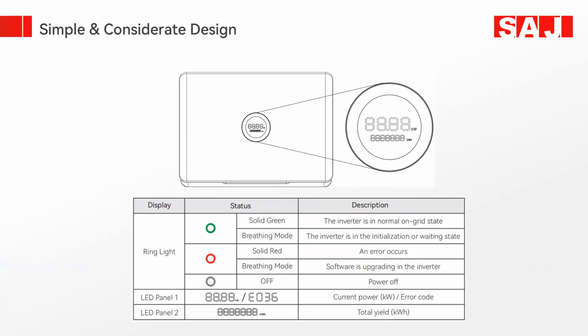LED panel 1, which is on the screen of the inverter, shows the current power or the error code. If the error is E024, it means grid loss. The grid is not available at site. LED panel 2 denotes the total yield in kilowatt hour. From when you configure the inverter until now, the total energy yield, like 1000 units and 2000 kilowatt hour, the inverter shows to the customers.